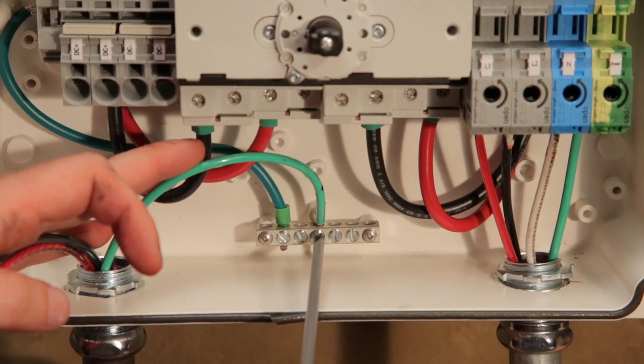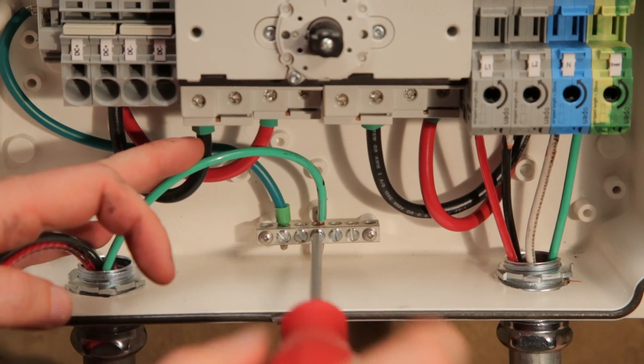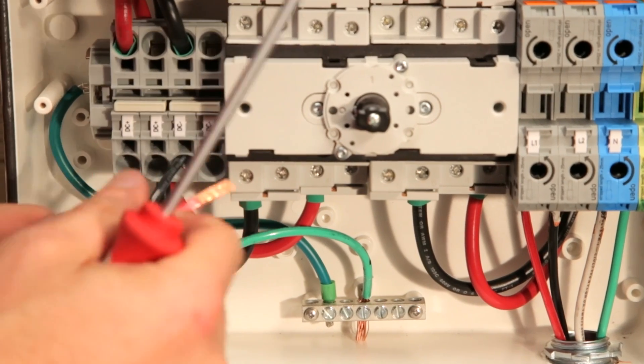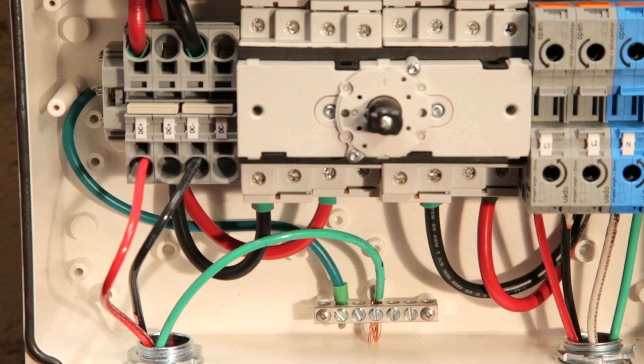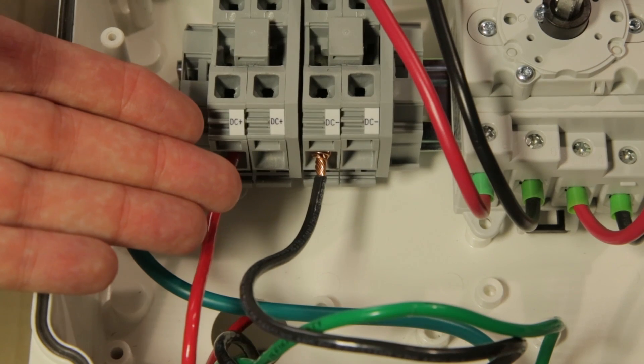Connect the DC equipment ground conductor to the equipment grounding terminal blocks in the AC DC safety switch. Connect the DC wires from the PV array to the DC positive and DC negative terminal blocks. Use a standard straight bladed screwdriver to connect the wires to the spring clamp terminals. Insert the wire fully — no exposed copper should be showing.